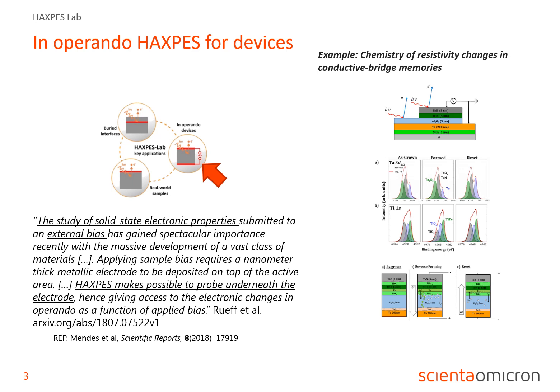They study solid-state electronic properties by utilizing HAXPES. The large mean-free path, which gives the large probing depth, allows them to probe right through a 15 nm electrode in a conductive bridge memory sample, and study the chemistry of resistivity changes underneath the electrode as a function of applied bias. This type of in-operando studies are also possible to make with the HAXPES lab. The manipulator allows for biasing the sample, and even adding additional contacts to the sample stage.